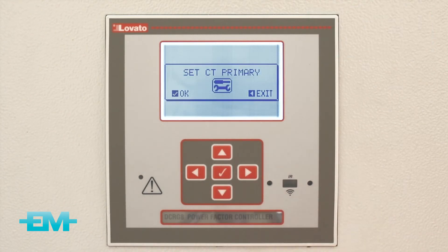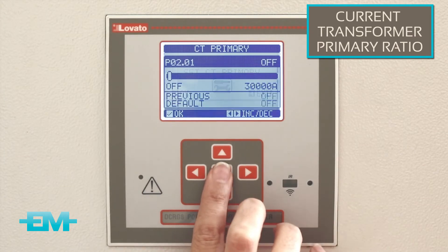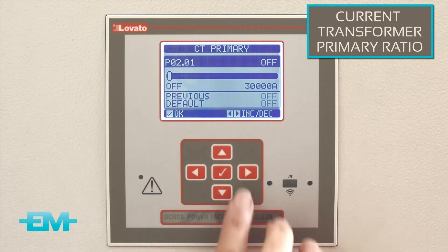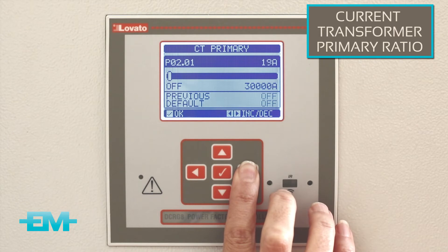Now we're going to set the current transformer primary ratio. In this demonstration we will set this to 350. Press OK to move on to the next screen, then use the right button until you reach the desired setting and press OK. This will take you to the main page.